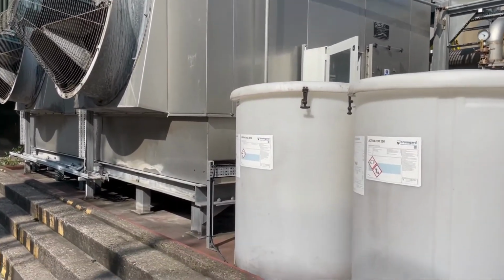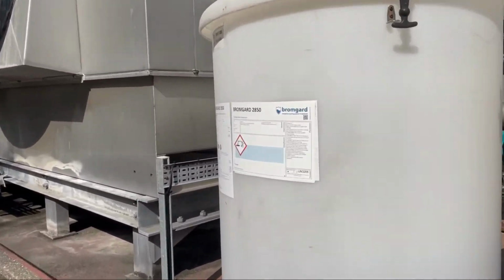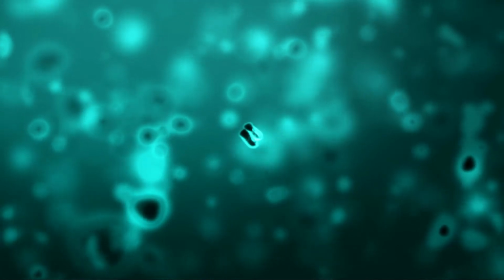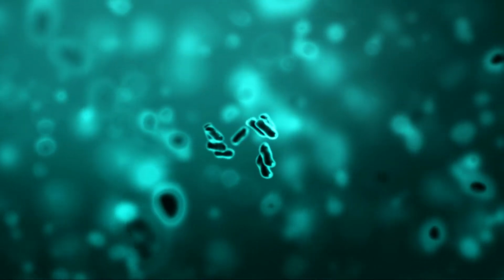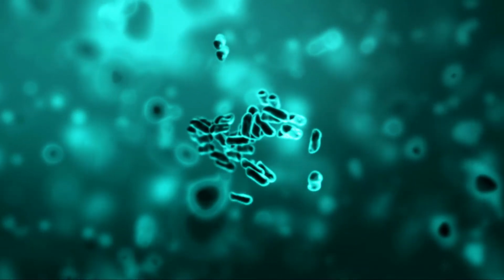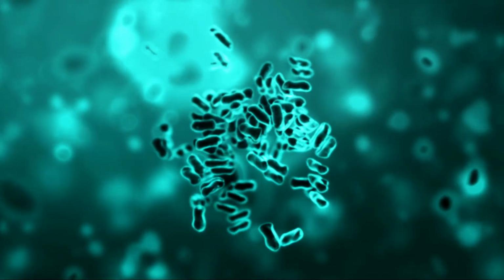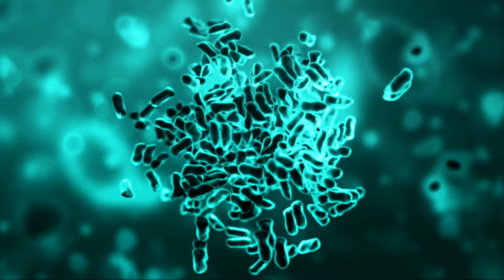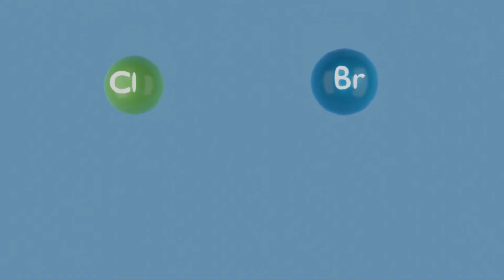protected. One of the key aspects of cooling water treatment is effective biocidal control to inhibit the growth of harmful or troublesome microbes such as Legionella bacteria or slime-forming biofilms. This is best achieved by the continuous dosage of a powerful oxidizing biocide, such as chlorine or bromine.